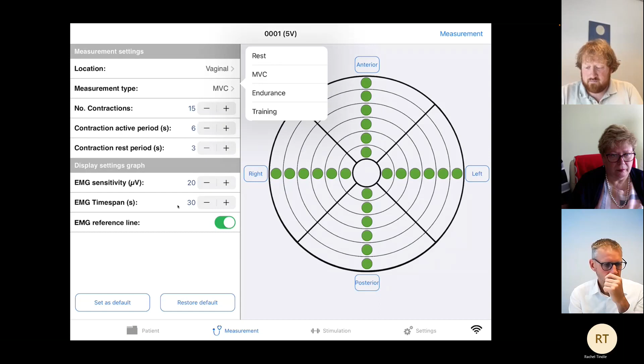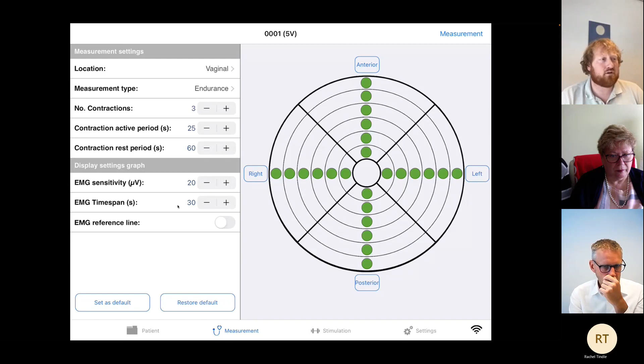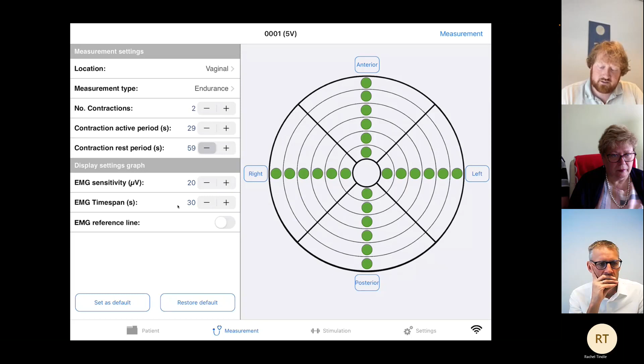Now, if I do an endurance measurement, it's the same principle, except that the active and the rest periods are different, so much longer, 25 or 30 seconds. From a factory setting, the data is 30 seconds active and rest 60. If you have different requirements, both for MVC or something else or for rest, you can modify the data with plus and minuses, and you can also set them as the standard value. So if I set it to 25 seconds and I set it as default for all the next measurements you are performing with all patients, these will be the default settings for an endurance measurement. Just so. Then again, on the right side, you have the grid.